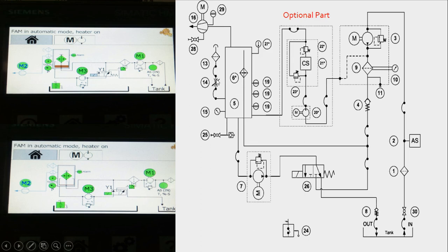This is the air filter needle valve to adjust the vacuum and pressure in the vacuum column. This is the drain valve, which helps to drain our tank for maintenance purposes. This is the evacuation pump, you can also say drainage pump. It circulates the oil within the vacuum column and it shifts the clean oil back to the tank.